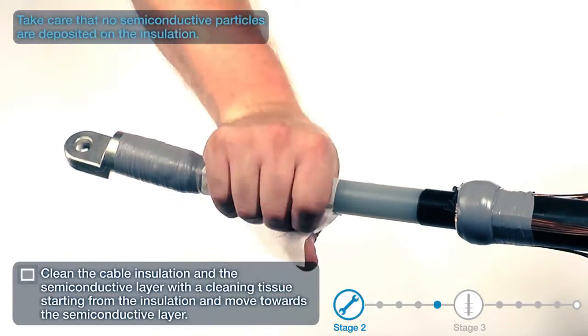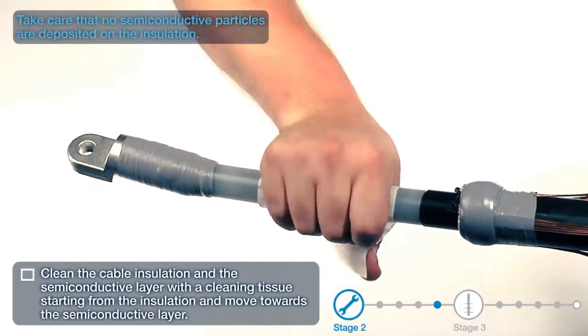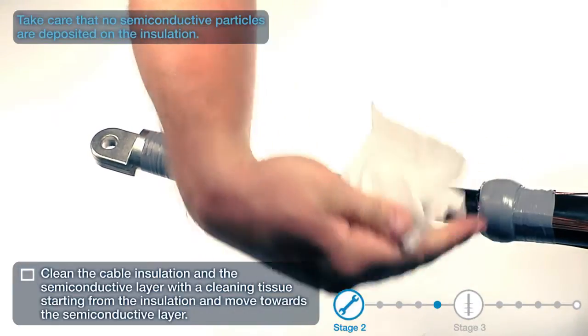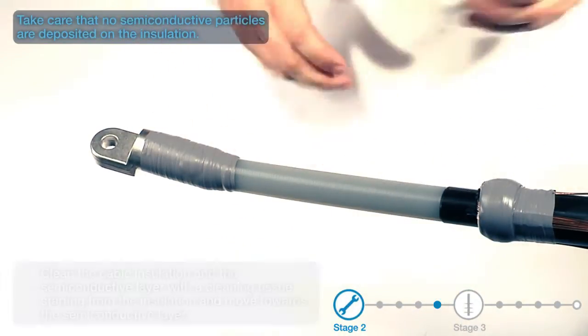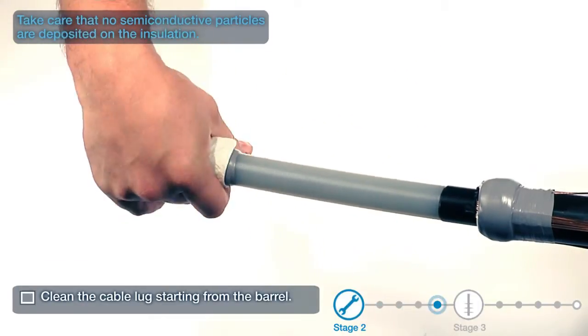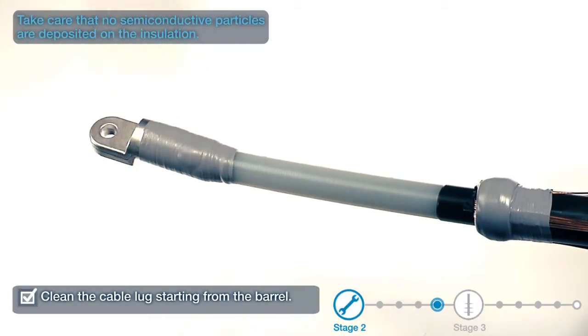Clean the cable insulation and the semi-conductive layer with a cleaning tissue, starting from the insulation and moving towards the semi-conductive layer. Clean the cable lug starting from the barrel. Take care that no semi-conductive particles are deposited on the insulation.